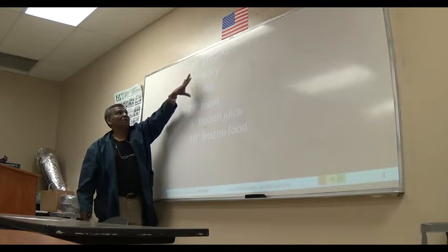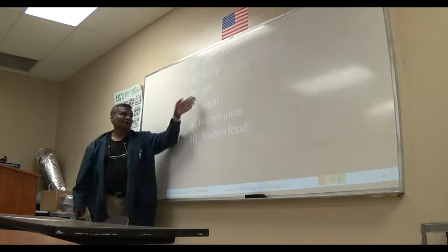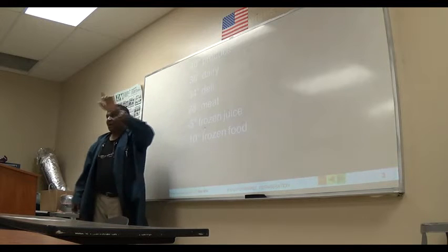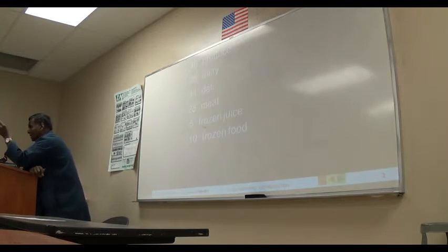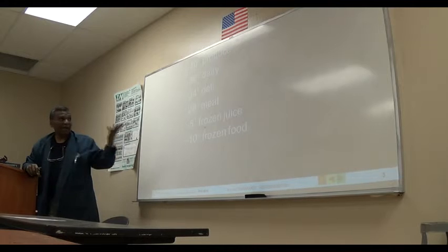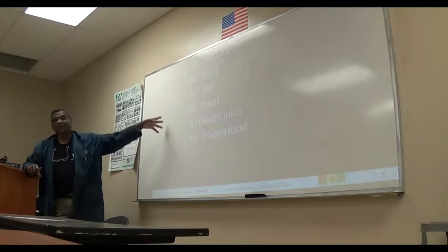Now, bear in mind one thing, guys. When we talk about this, this is your product or your box temperature, 40 degrees for produce. When we were in your air conditioning class, what was the temperature difference between the air going into that coil and the refrigerant boiling point? 35 degrees between the refrigerant boiling off in the coil and the air going across the coil.